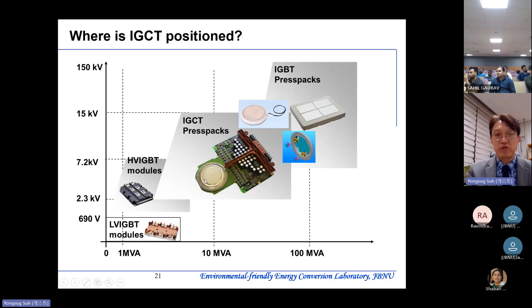What are the advantages of IGCT? Because of the GTO thyristor structure, it has high current turn-off capability, almost 3 times as high as IGBT. That means if you need 3 IGBTs in parallel, you can simply use 1 IGCT, simplifying the mechanical bus bar and cooling system. As I mentioned, it's not only the electrical system but also the cooling and mechanical system that add a lot of cost, so it's important to streamline and simplify the mechanical bus bar connections.